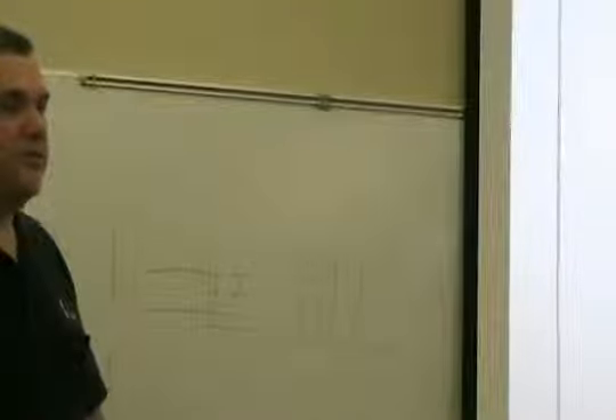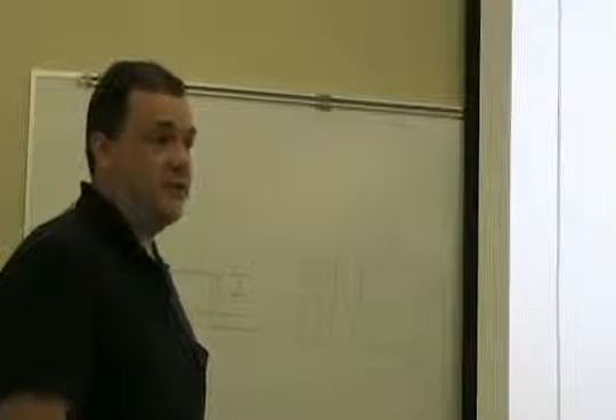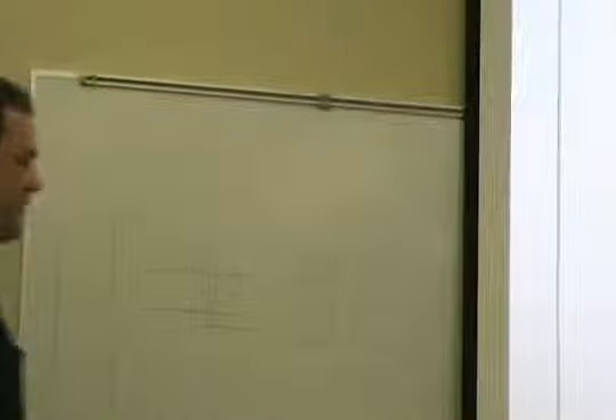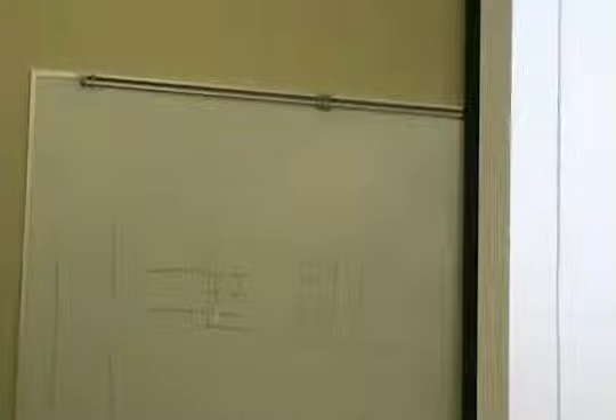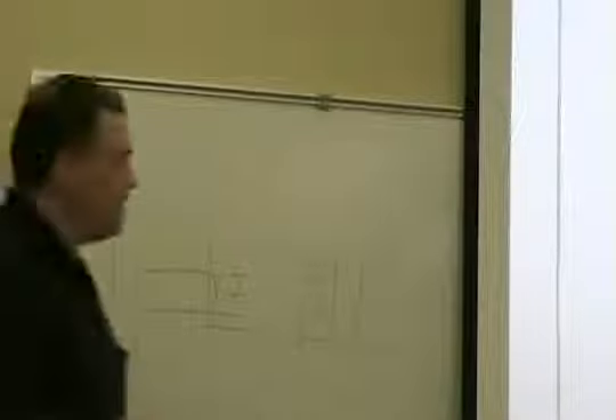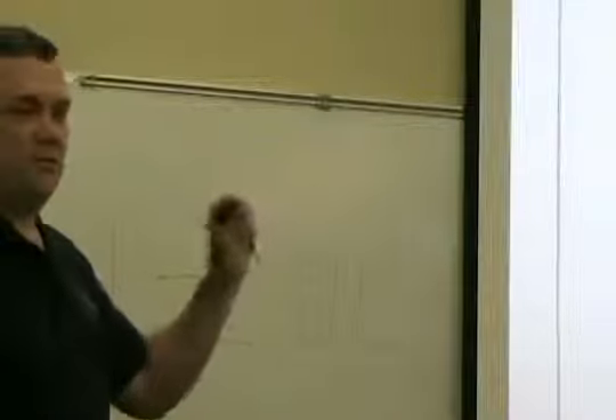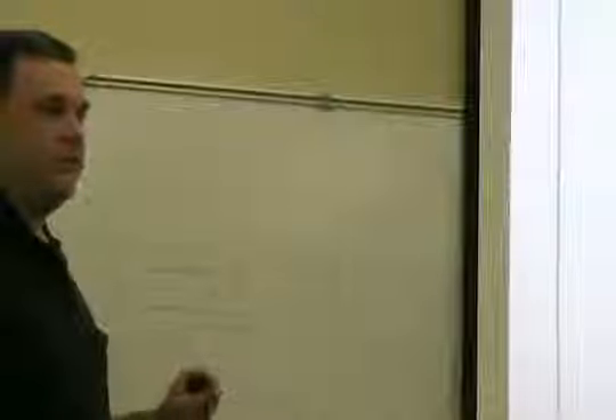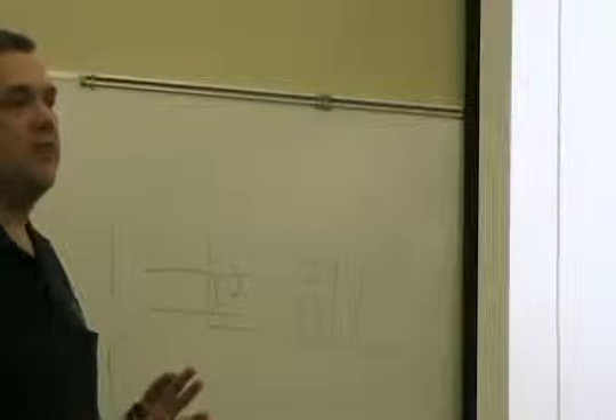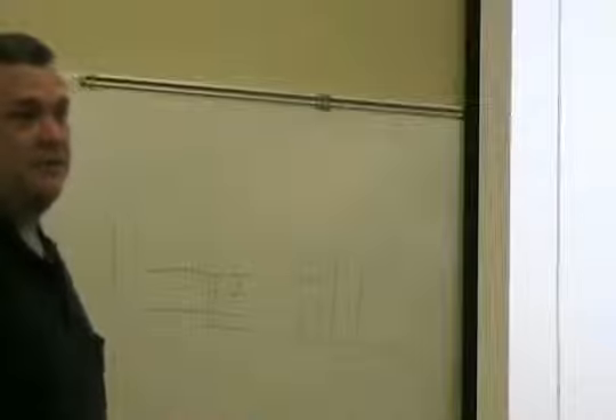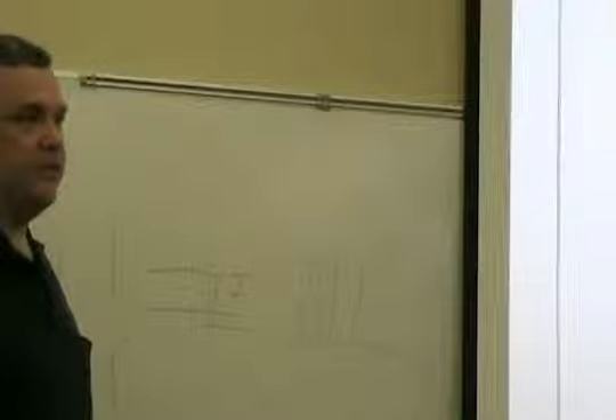That's not as critical though as if you have a balance man come balance it, he's gonna put the flow coefficient in there correctly. Because even if I know that flow coefficient, that amplification, the balance man's still gonna tweak it up or down just a little bit to get it as close as he can. Okay? The weirdness is that you're gonna have 1,000 VAV boxes with a flow coefficient close to one number, and then one with a flow coefficient that may be totally different. And it's correct. Okay? So that'd be the only caution if you're going to a different airflow sensor.